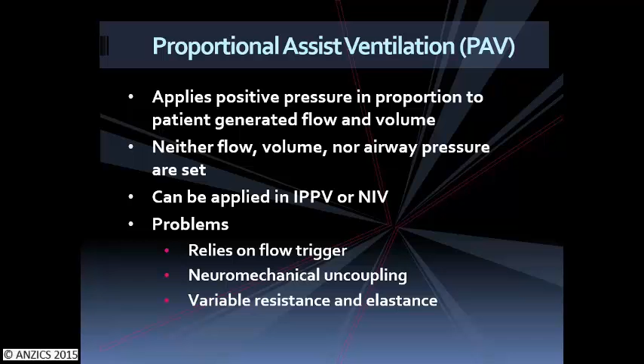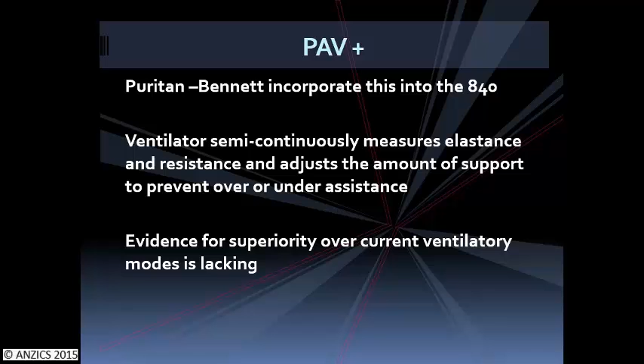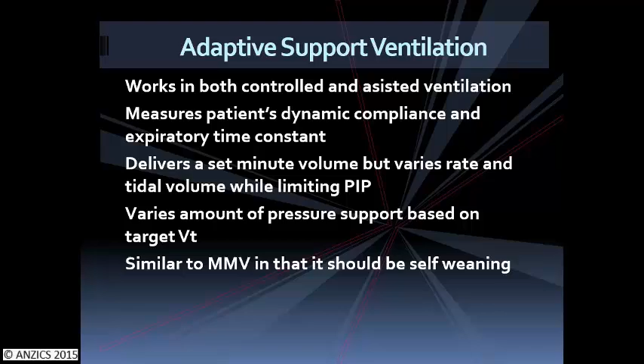And they call it that. And the PAV plus is the one where it will measure or intermittently measure compliance and resistance and adjust the amount of support based on those measurements. And then there's adaptive support ventilation, which again gives you support based on the effort of breathing that you make, which is probably, I don't know if it's a good thing or a bad thing, but again, it's not been shown in any trial to make any difference to your ability to get off the ventilator or the speed of weaning.